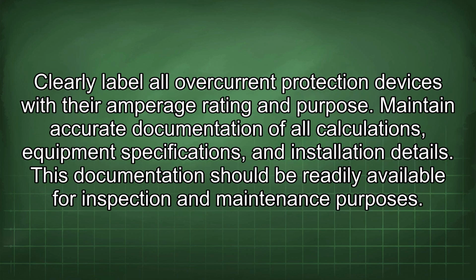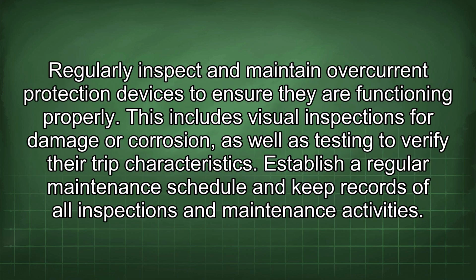Clearly label all overcurrent protection devices with their amperage rating and purpose. Maintain accurate documentation of all calculations, equipment specifications, and installation details. This documentation should be readily available for inspection and maintenance purposes. Regularly inspect and maintain overcurrent protection devices to ensure they are functioning properly. This includes visual inspections for damage or corrosion, as well as testing to verify their trip characteristics. Establish a regular maintenance schedule and keep records of all inspections and maintenance activities.